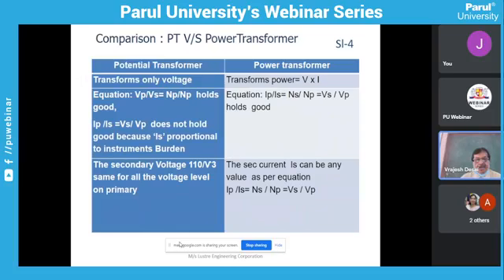And now the secondary voltage in case of CVT is 110 or 110 by root 3 for all the voltage levels, whether it is 800 kV, 400 kV, 220 kV, 245 kV, or 145 kV. In case of power transformer, the secondary current can be any value as per the equation, as per the load which is connected to the transformer.